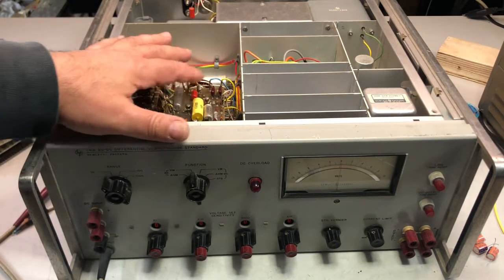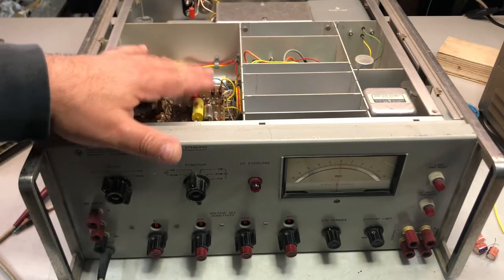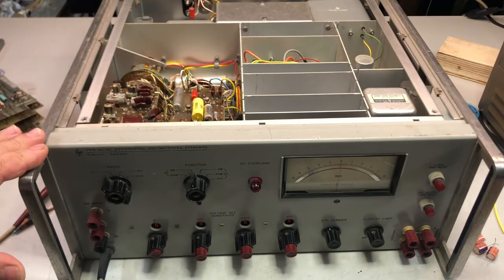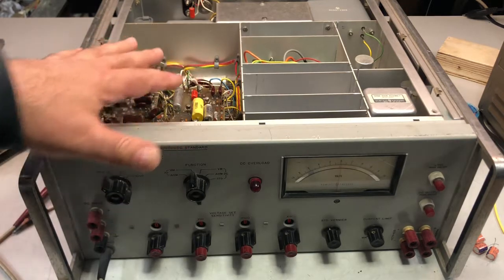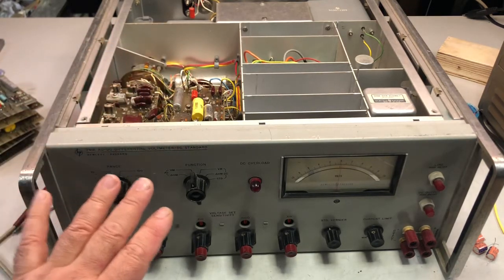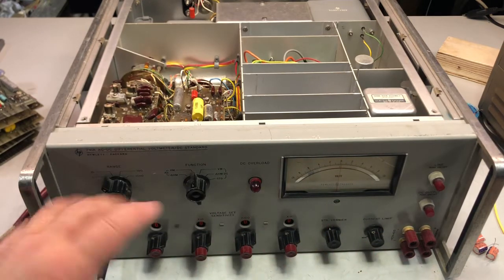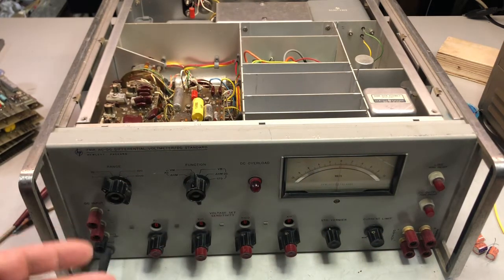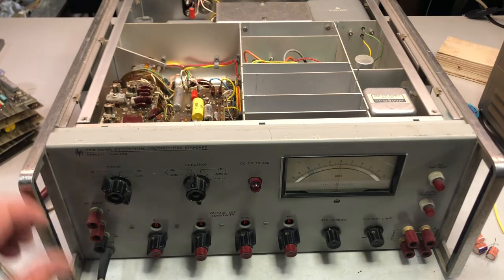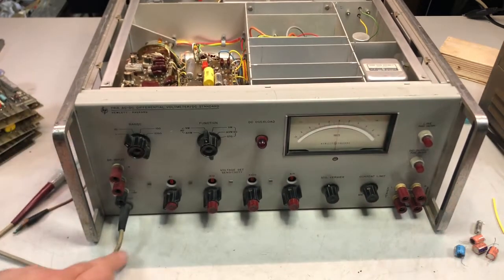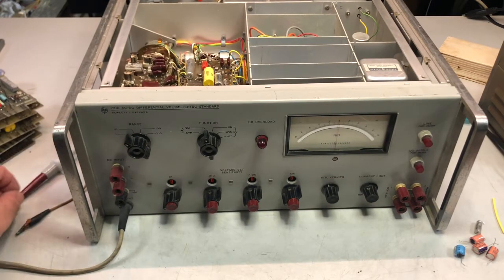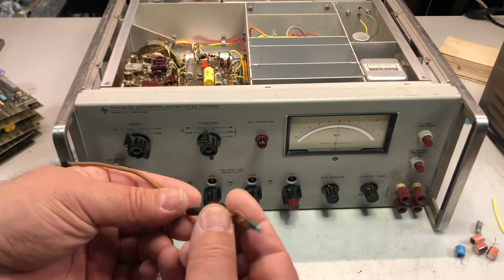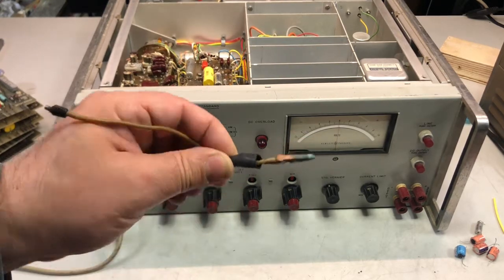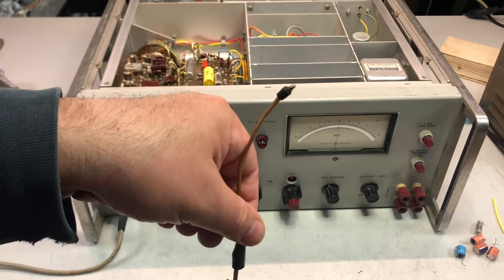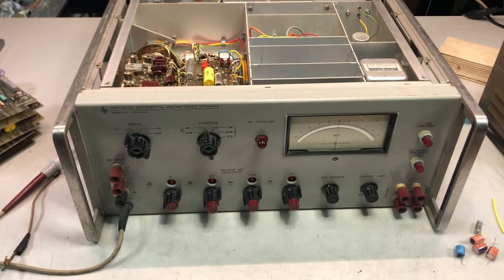This is the preamplifier board, so it must be a very clean signal inside this board. So I want to take care about that. While I'm continuing the capacitor checking, I want to clean the front panel in order to be used without any problem, as well as the cord here of the probe, which is very dirty and nasty, and I want to replace this very bad alligator at the end of the ground strip of the probe.